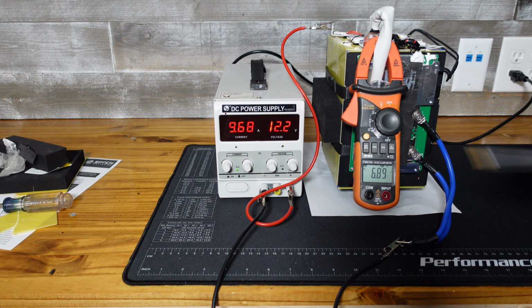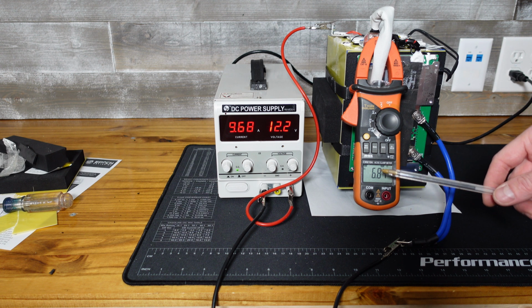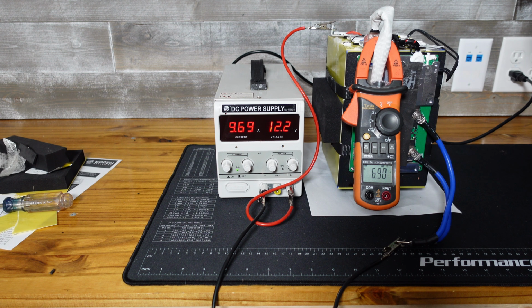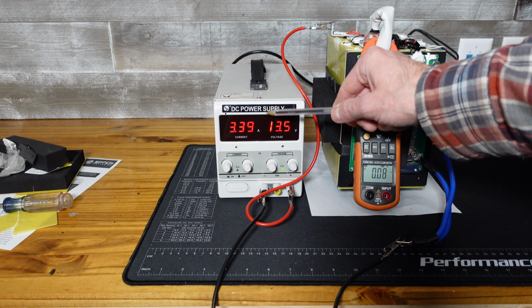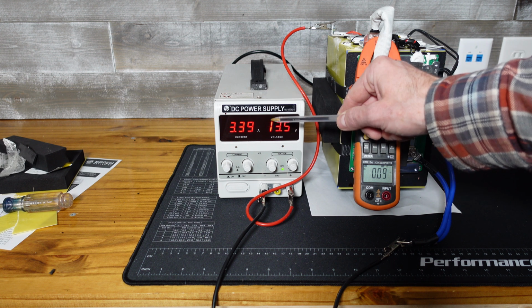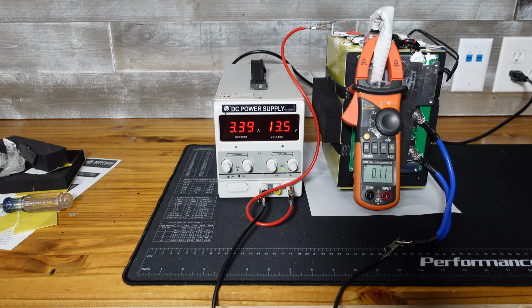Okay, so 2 seconds, we see our current drop to 6.9 amps. So we know that heater is on, but I'm expecting to see that actually shut off completely. Let's try that again here. Okay, so now the charging has stopped, but we're still taking 3.4 amps out of this power supply. So that power there is going to be what those heaters are consuming.